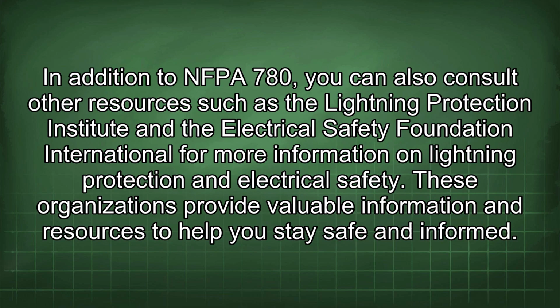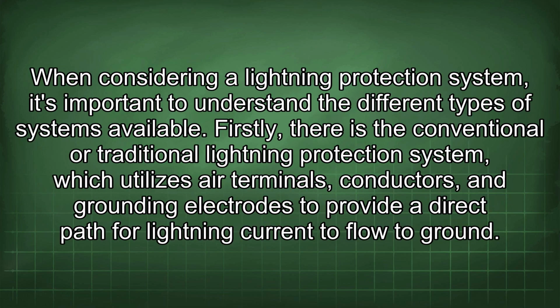In addition to NFPA 780, you can also consult other resources such as the Lightning Protection Institute and the Electrical Safety Foundation International for more information on lightning protection and electrical safety. These organizations provide valuable information and resources to help you stay safe and informed. When considering a lightning protection system, it's important to understand the different types of systems available. Firstly, there is the conventional or traditional lightning protection system, which utilizes air terminals, conductors, and grounding electrodes to provide a direct path for lightning current to flow to ground.